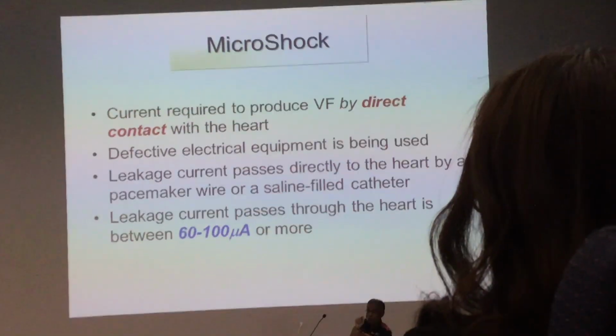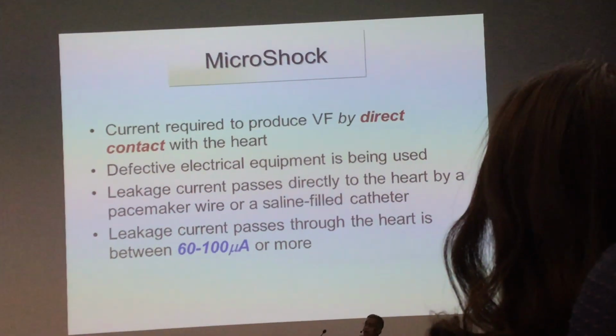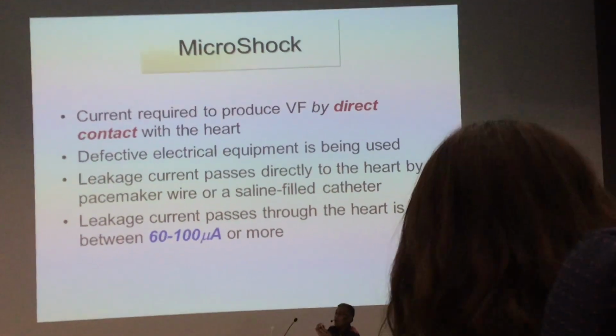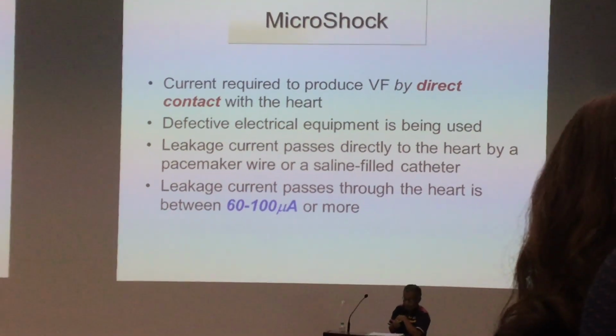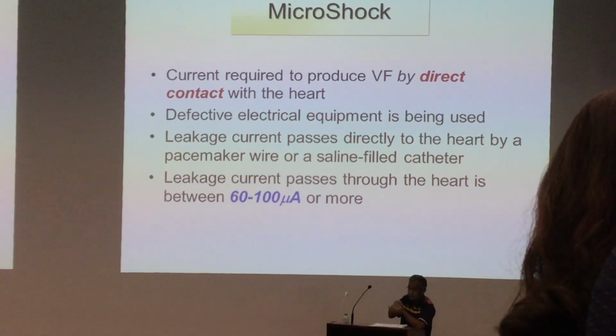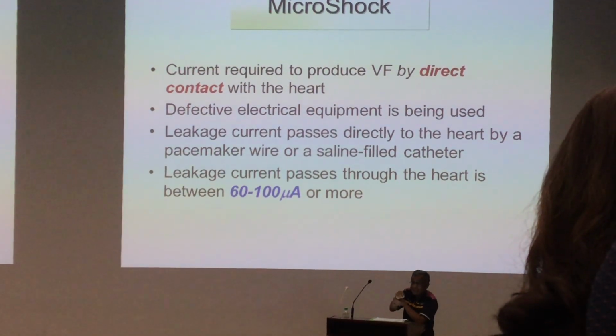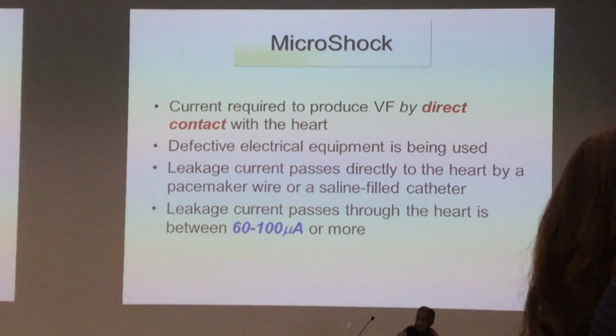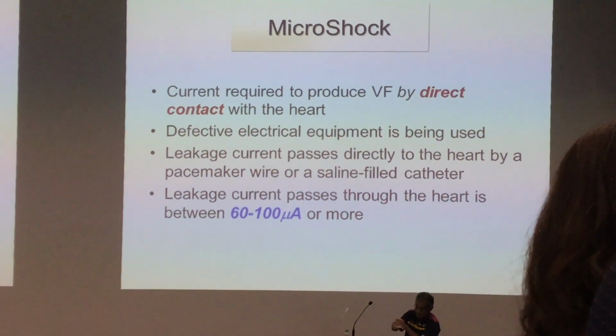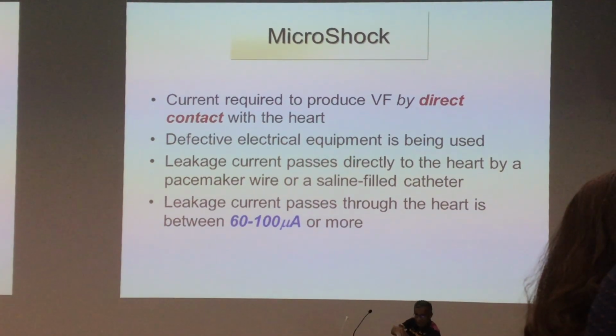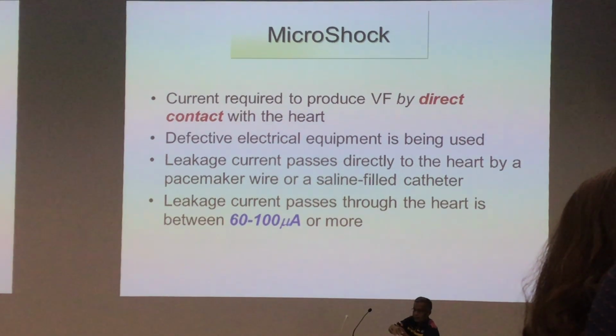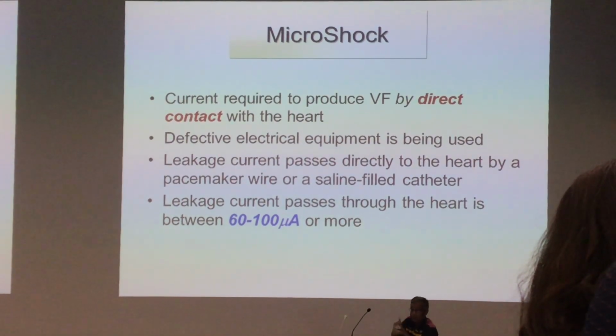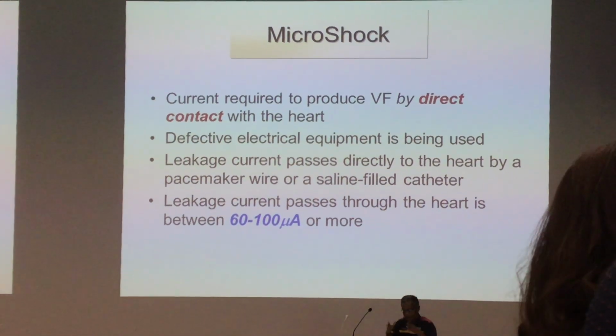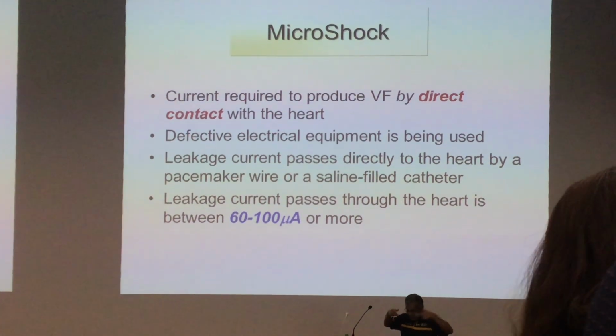Microshock is different. It occurs when there's direct contact to the heart. For example, the CVP catheter, your pacemaker catheter, or when you are operating directly onto the heart, CABG, which means there's direct contact with the heart, and there's a faulty machine, the current passing through the saline catheter, or passing through the pacemaker cable, or passing through the knife or scalpel or artery which is in contact with the myocardium, you get microshock. In other words, you have a current directly in contact with the heart.